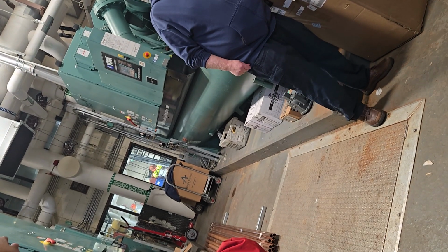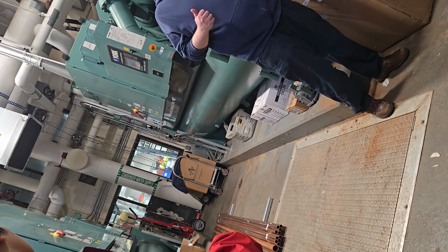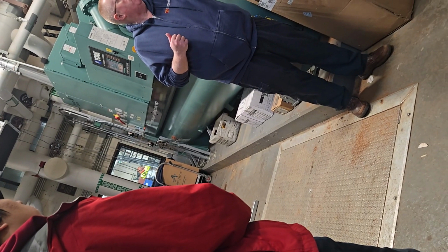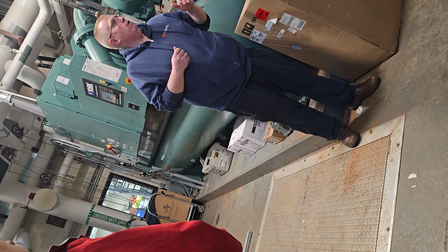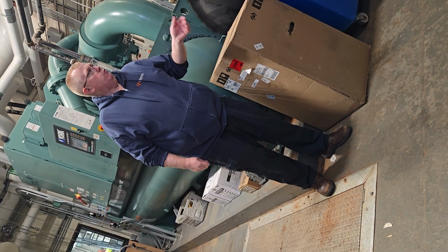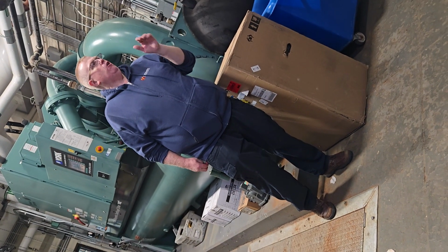Oh yeah, they are. They spend money no matter how you slice it, because the main campus, like right now, we are using mechanical cooling because the outside temperature has got above a certain dew point. We run it off of a temperature and dew point relationship. Yeah, humidity is the key. So when humidity is high, you may not have enough with the free cooling.